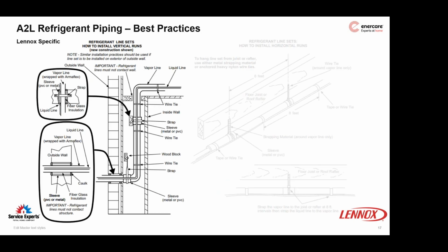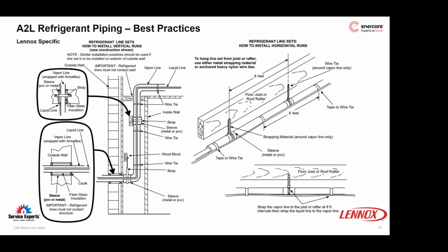And then here are a couple of images out of that piping guideline document showing how they isolate the piping system from the actual structure of the building so that it doesn't cause creaking and cracking, unusual rubbing, or unusual wear and tear on the piping system. Again, this isn't exclusive to Lennox. I've seen this in the Carrier and the Goodman manuals as well, where they hang rather than strap to the joist as a suggestion, so that when there's expansion and contraction on the piping system, it can move freely. It's not restricted by being strapped tightly against a joist.